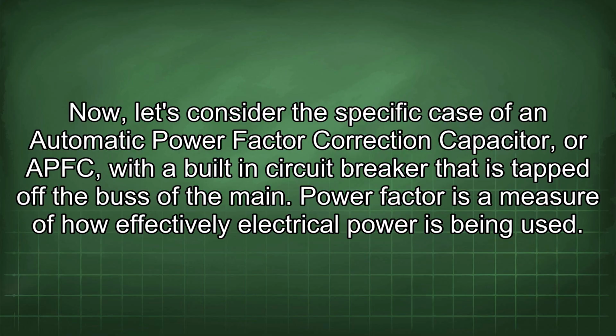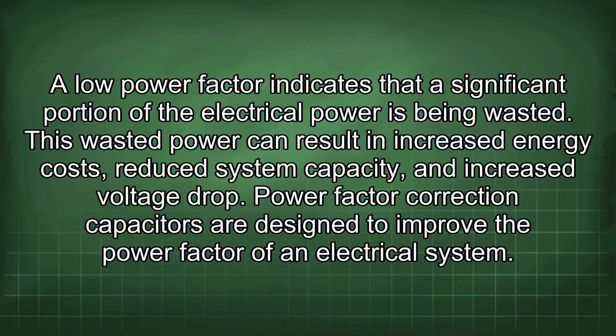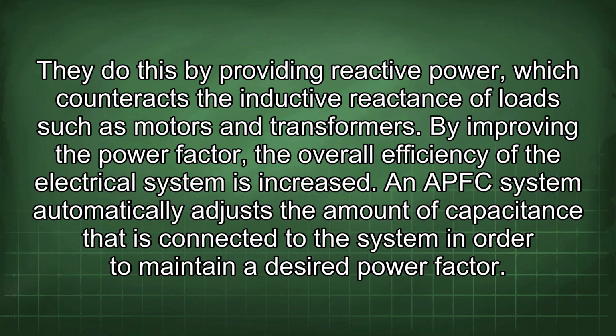Power factor is a measure of how effectively electrical power is being used. A low power factor indicates that a significant portion of the electrical power is being wasted. This wasted power can result in increased energy costs, reduced system capacity, and increased voltage drop. Power factor correction capacitors are designed to improve the power factor of an electrical system. They do this by providing reactive power, which counteracts the inductive reactance of loads such as motors and transformers. By improving the power factor, the overall efficiency of the electrical system is increased.